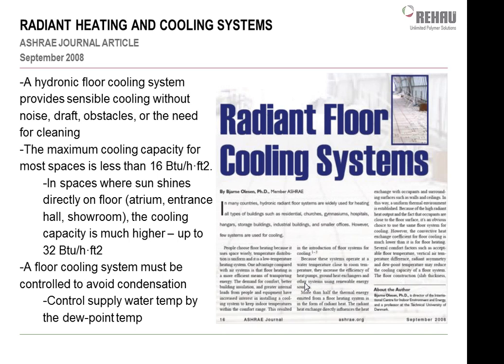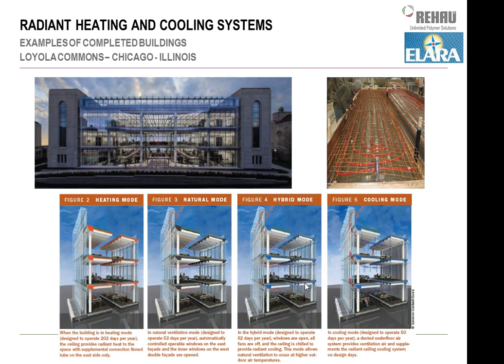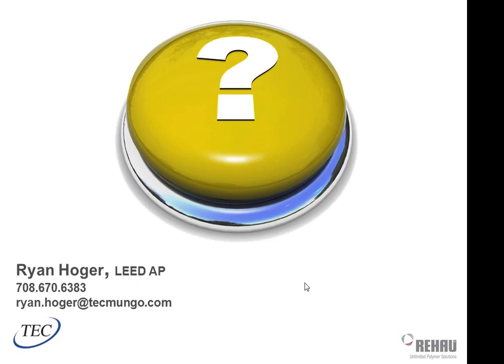Here's an article you can look at from 4 years ago now in the ASHRAE Journal on radiant cooling systems. If you're laying out a radiant cooling system, let us know. We have a guy over at REHAU that designs quite a few of these, and he can help us lay these things out, or help you lay these things out if you're designing one. We do have one in operation here locally that ELARA engineers did at the Loyola Commons building. It's Loyola University, right on the lakefront. You've probably seen the building before. It's basically a library and student studies type center, and it's mostly a glass building, and they're doing that with radiant cooling and heating with REHAU PEX tubing.